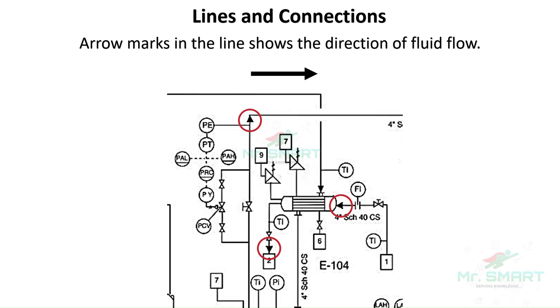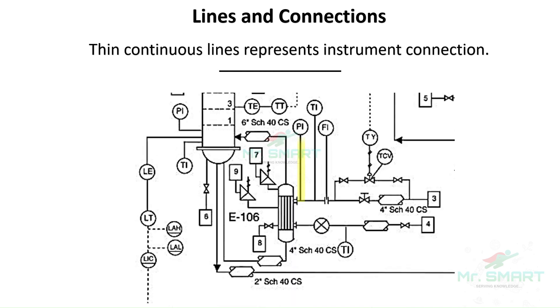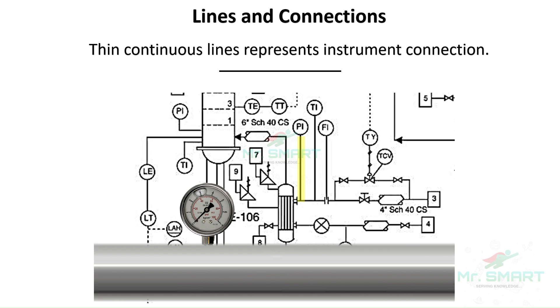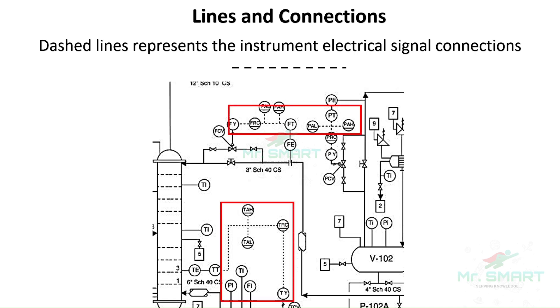Have you noticed the arrow marks over the lines? These arrow marks show the direction of fluid flowing inside the pipe. The thin continuous lines in the P&ID represent the instrument connection with pipes or equipment. In some cases, these lines will not be comparatively thin, as the instrument connections are also done in the form of piping. A continuous dashed line in a P&ID represents instrument electrical signal connections. These instruments are connected only with electrical signal wires, and there is no physical piping connection between them.